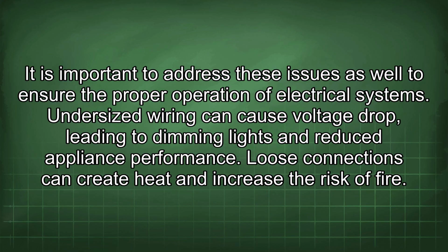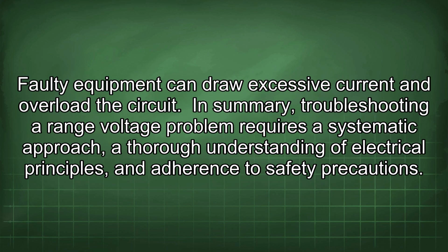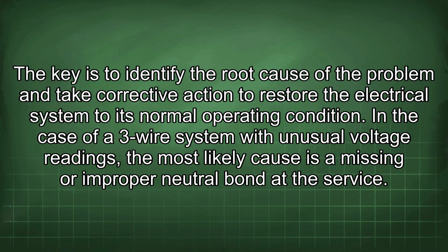Undersized wiring can cause voltage drop, leading to dimming lights and reduced appliance performance. Loose connections can create heat and increase the risk of fire. Faulty equipment can draw excessive current and overload the circuit. In summary, troubleshooting a range voltage problem requires a systematic approach, a thorough understanding of electrical principles, and adherence to safety precautions. The key is to identify the root cause of the problem and take corrective action to restore the electrical system to its normal operating condition.